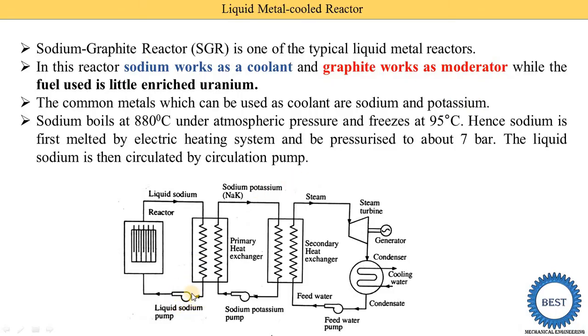Sodium is first melted by an electric heating system and pressurized to about 7 bar. Before putting sodium into the primary circuit, we melt it in an electric heating system. Then this liquid sodium is supplied to the reactor using a liquid sodium pump, and the pump circulates it through the system.